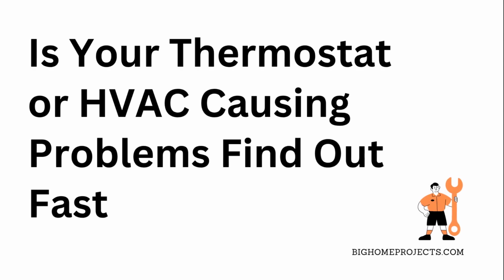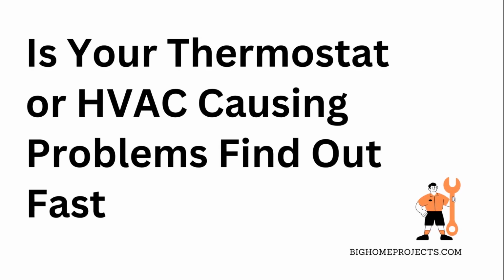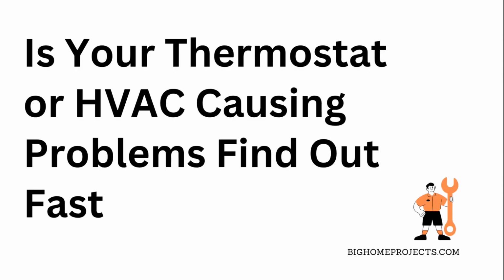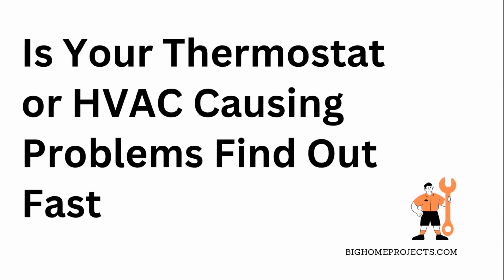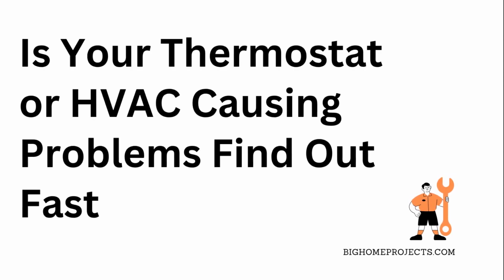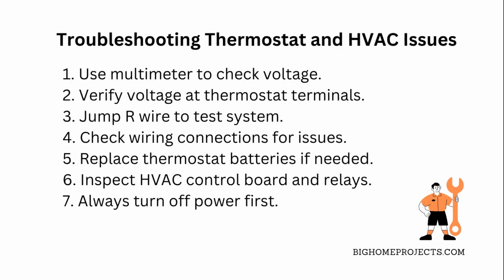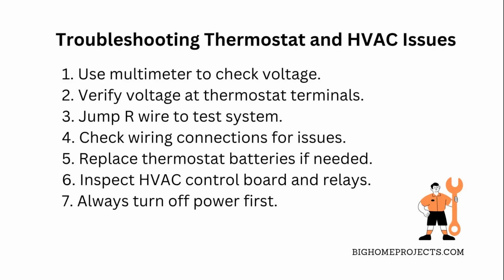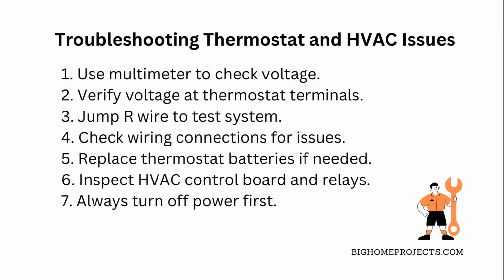If your heat or AC isn't kicking on right, figuring out whether the thermostat or HVAC system is the culprit can seriously save you time and cash. So, first off, grab a multimeter. It's like your best friend for this kind of troubleshooting. Check if you're getting 24 volts at the control board. This tells you if the thermostat is sending power like it should.